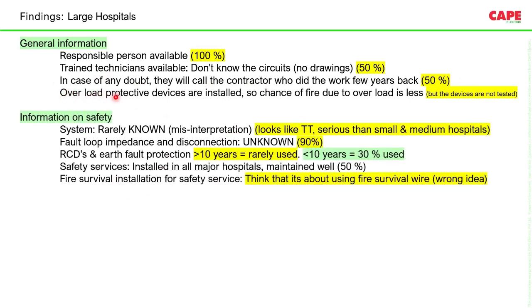In these cases, overload protective devices are installed. Protective devices such as, from the starting, for example, air circuit breaker, molded case, MCCB, MCB, fuses, all those things are installed. So the chance of fire due to overload is mostly less in this particular case because proper devices are there. Unfortunately, the devices are not tested. So we really don't know whether these devices will trip or not.